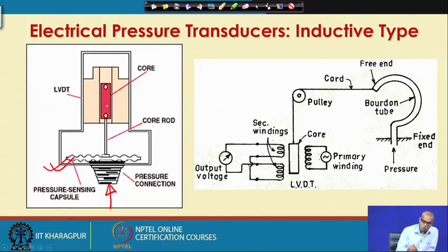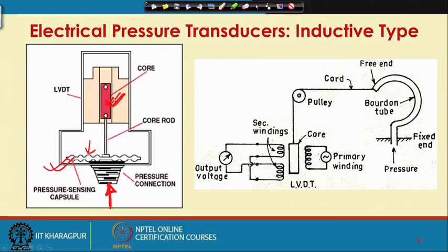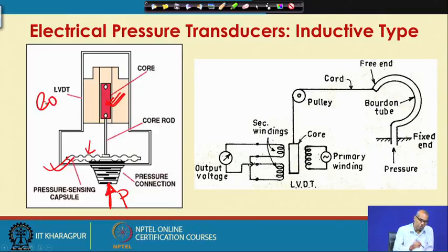Here the core of the LVDT is connected to this pressure sensing capsule. Now, when I apply pressure here, this capsule receives the pressure and it will show deflection. So, this displacement will cause a movement of the core of the LVDT. So, the LVDT will produce an electrical signal, a voltage, and that will be dependent on the pressure being applied. So, I can directly calibrate the output voltage of LVDT with this pressure. These two can be directly related.